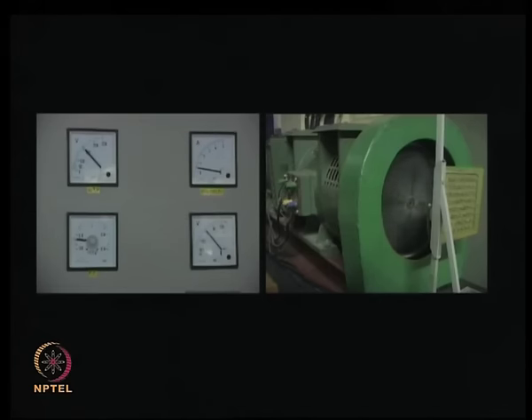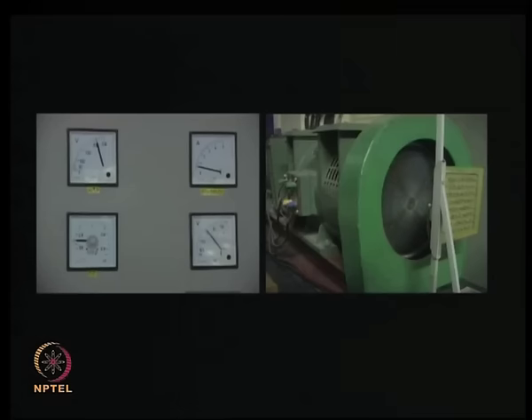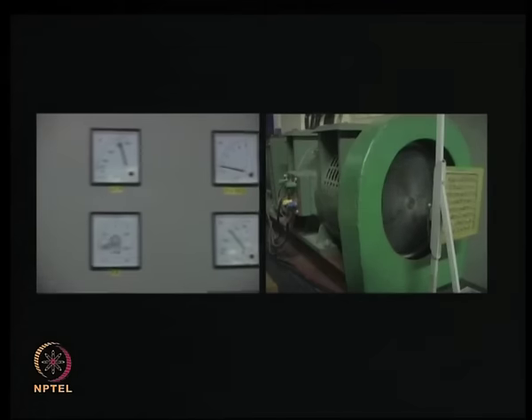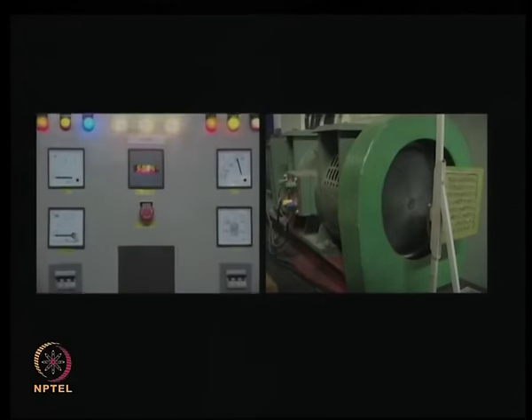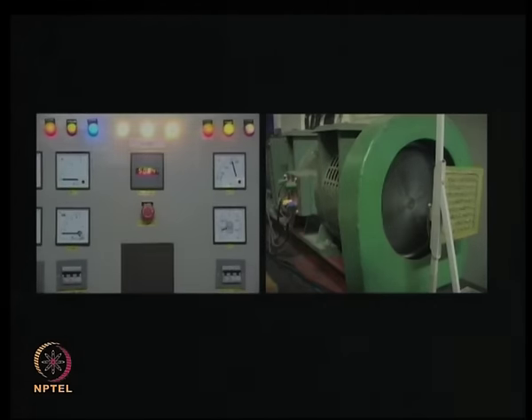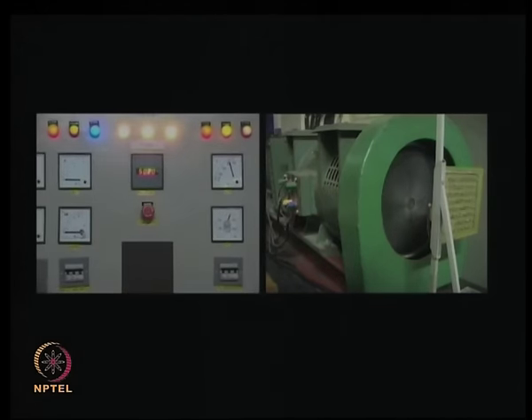We now give step changes to the voltage reference of the controlled field, so that we get the voltage near about 230 volts, which is roughly equal to the voltage of the lab power supply. We now switch on the laboratory supply, and as I mentioned some time ago, the dark lamps start glowing, and they blink and glow at a different frequency.